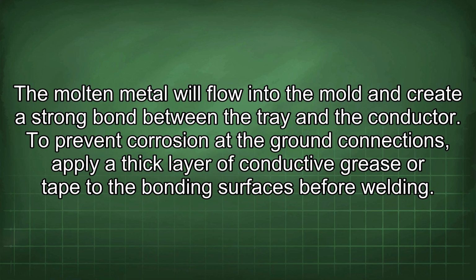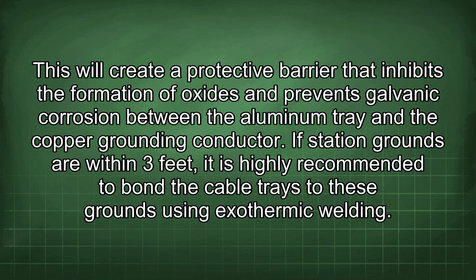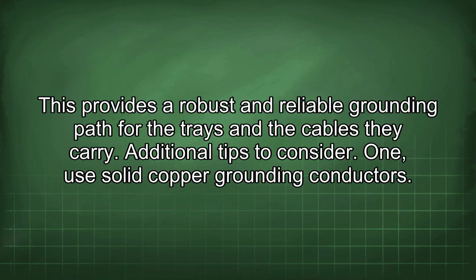To prevent corrosion at the ground connections, apply a thick layer of conductive grease or tape to the bonding surfaces before welding. This will create a protective barrier that inhibits the formation of oxides and prevents galvanic corrosion between the aluminum tray and the copper grounding conductor. If station grounds are within 3 feet, it is highly recommended to bond the cable trays to these grounds using exothermic welding. This provides a robust and reliable grounding path for the trays and the cables they carry.